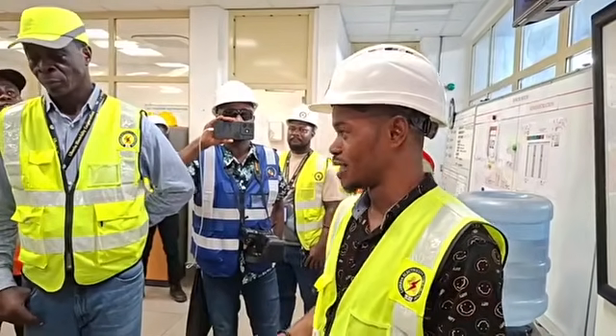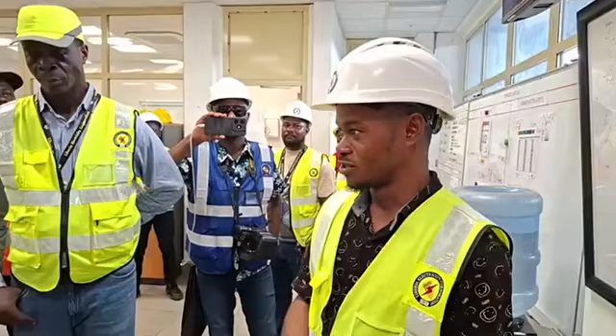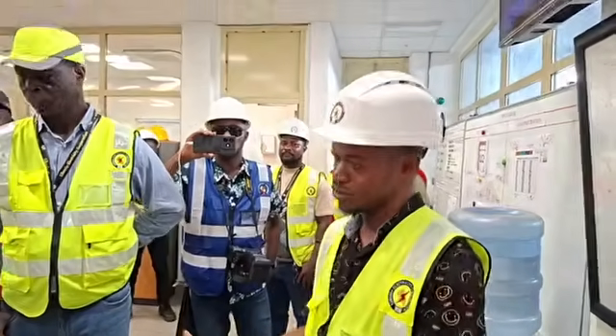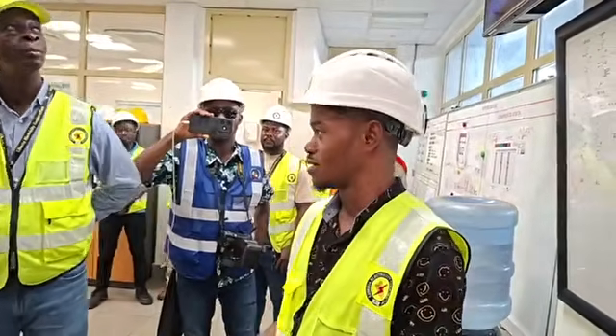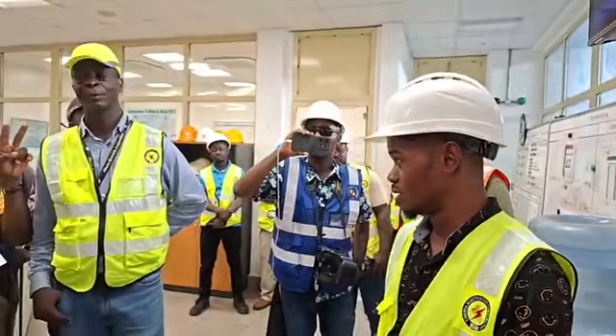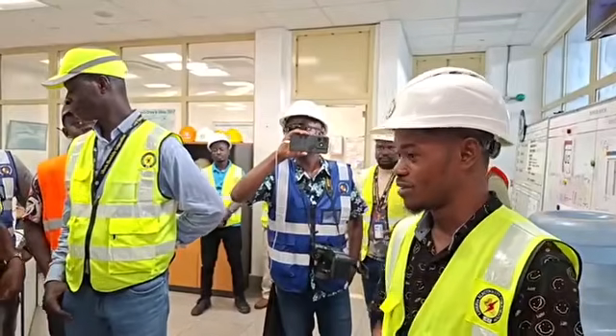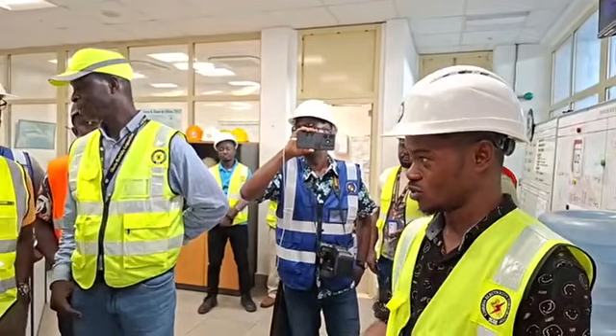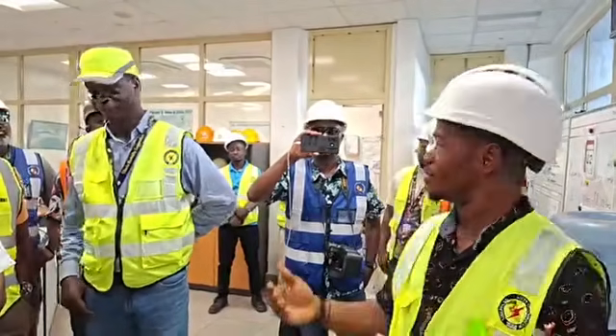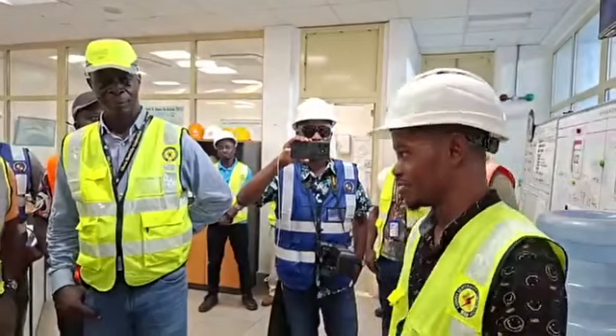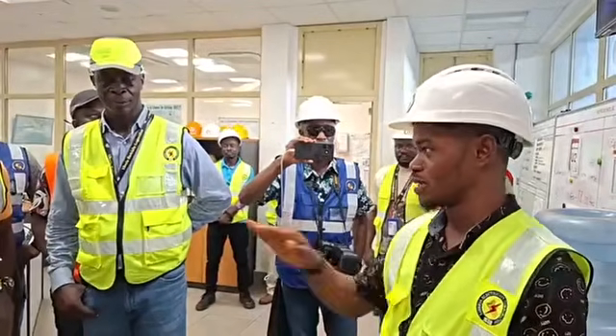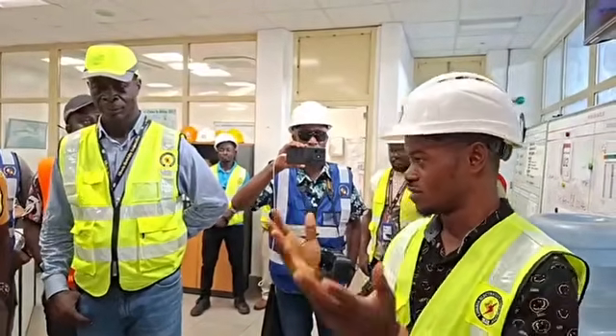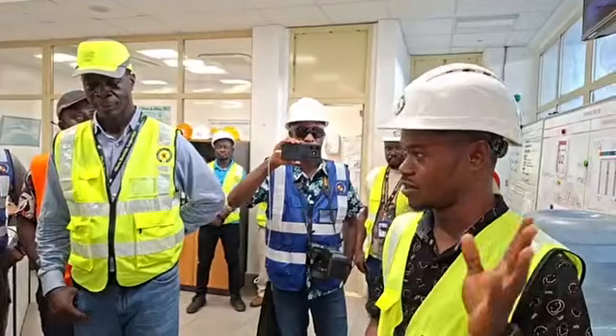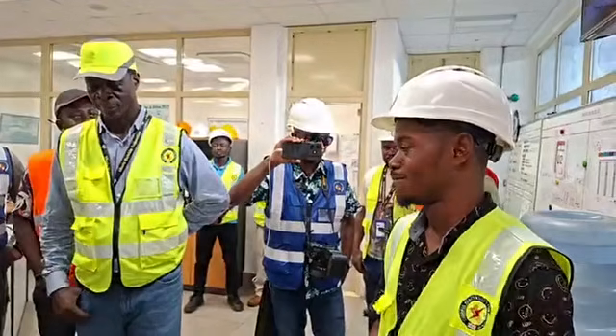Once we have a blackout, irrespective of whether we're in operation or on standstill for reservoir recovery, we come along and black start the grid, providing temporary supply. Once we get the Transco line back, we shut our unit down, go back into remote, and leave the grid with Transco and the crucial supply.